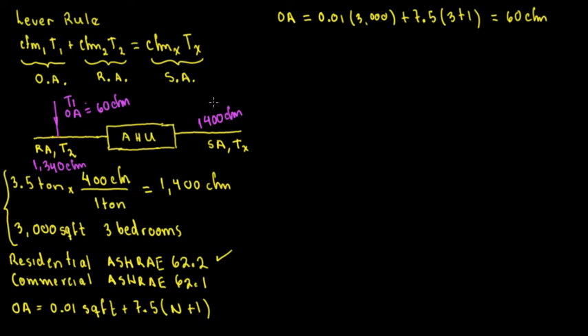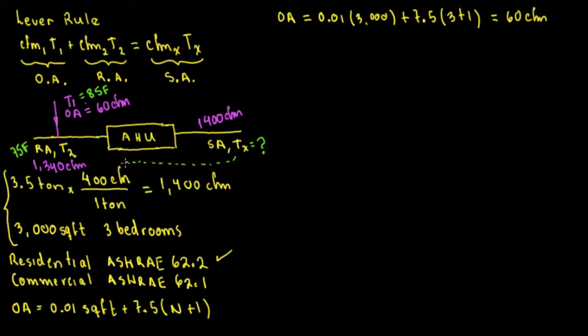To complete this example, we'll assume the outside temperature is 85°F — it's summer. The return air temperature is 75°F. What we're trying to find is the mixed air temperature right before entering the air handler unit, because once it passes the coil the temperature will be 55°F or less.